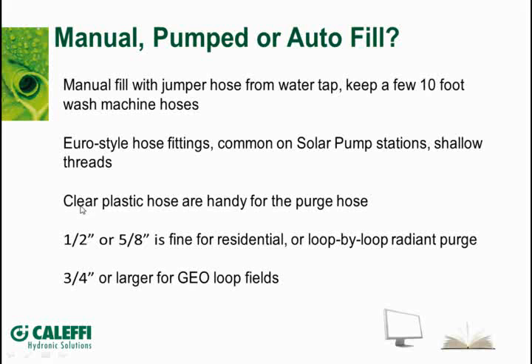Another tip, and I'll show you some of them here in a second, some clear plastic hoses are nice for purge hoses, so you can see what's coming out of the system. If you see there's a lot of copper debris, little copper shavings, you can probably assume that somebody cut it with a bandsaw, with a hacksaw, or maybe a chop saw, and some of that copper shaving was left behind in the system. For your typical residential job, a 1/2 or 5/8 hose is fine for purge and fill hoses, and that's what a typical washing machine hose is. A really handy hose to have in your truck. Have a bucket full of those for using for filling and purging out.